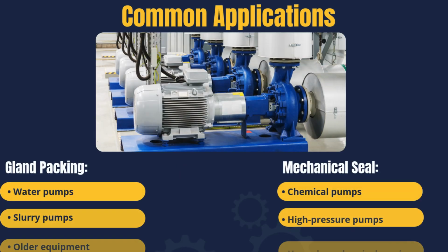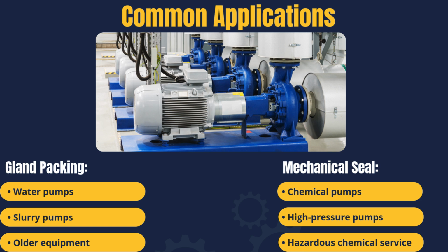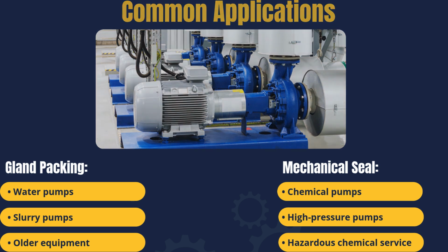Common applications: gland packing is used for water pumps, slurry pumps, older equipment. Mechanical seal is used for chemical pumps, higher pressure pumps, hazardous chemical service.